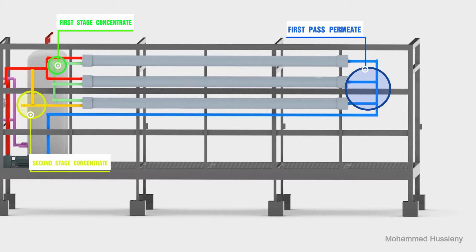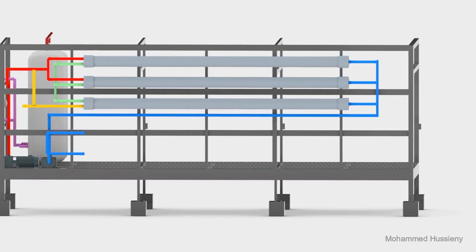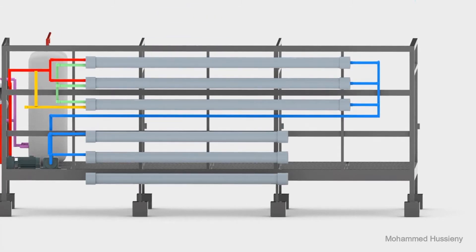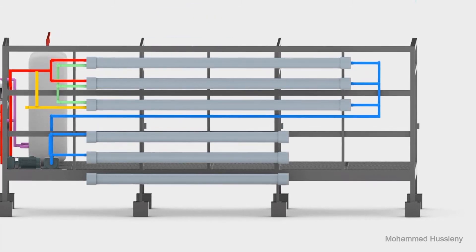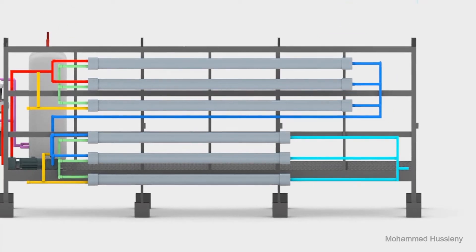The permeate flow of the first and second stages of the first pass gets pumped and fed to the second pass. Similar to the first pass, the second pass is composed of two stages, and the concentrate flow of the first stage is fed to the second stage. And the concentrate flow of the second stage gets recycled back to the RO system.